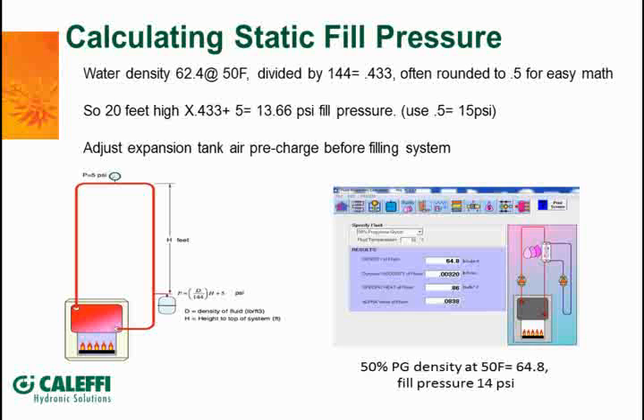All right, so we're going to fill a system. We've got a new job. We just put a boiler in this house. How much pressure do we have to put in the system? Well, how do we know when we've got enough pressure in the system? What the pressure that you're filling the system with does is it pushes the air up to the highest point in the system so you can evacuate, but that's what gives you the static fill pressure, is the pressure that you're putting into it.